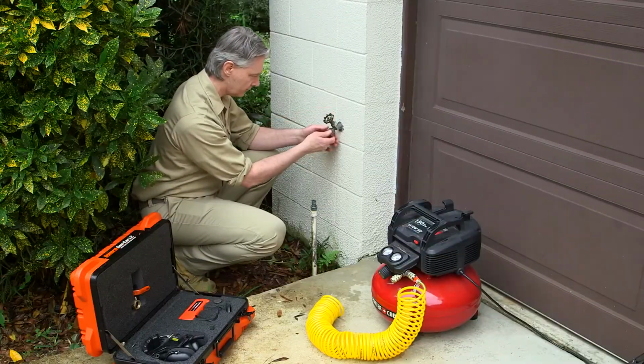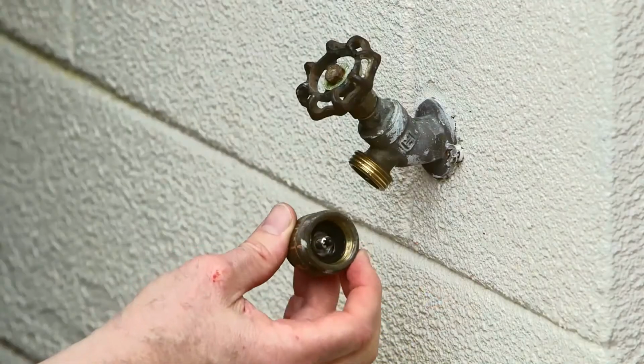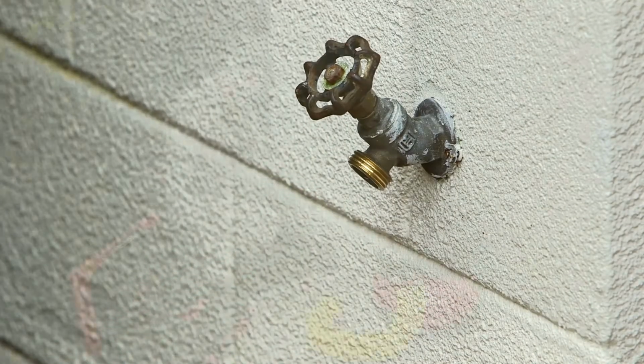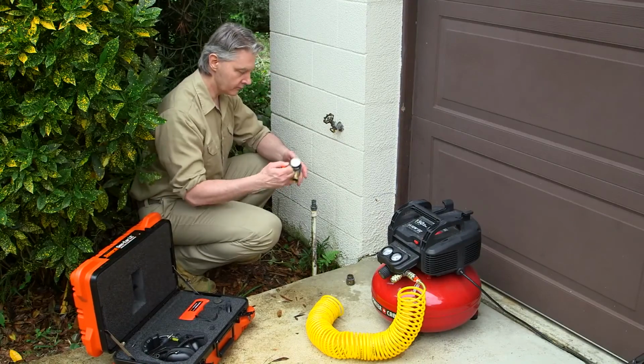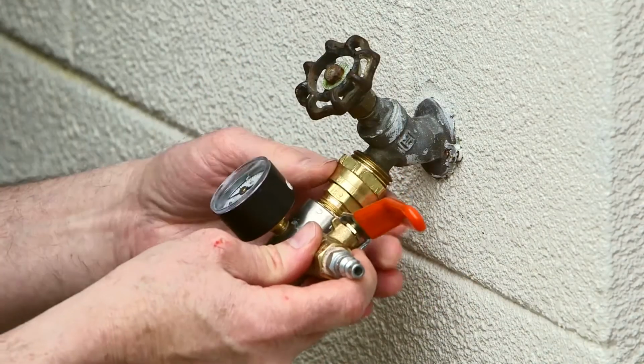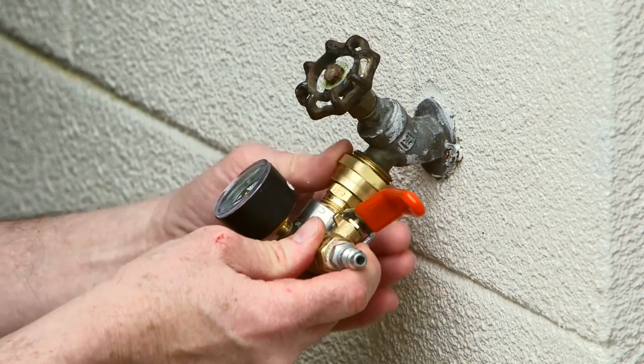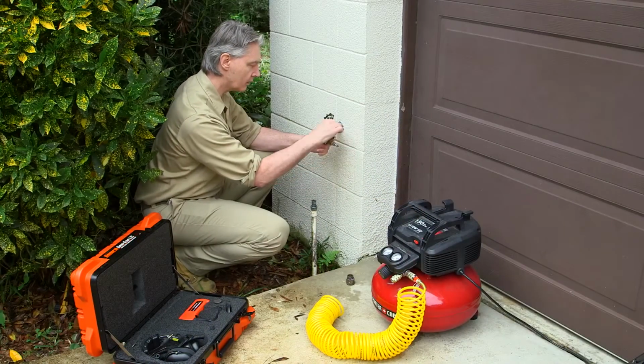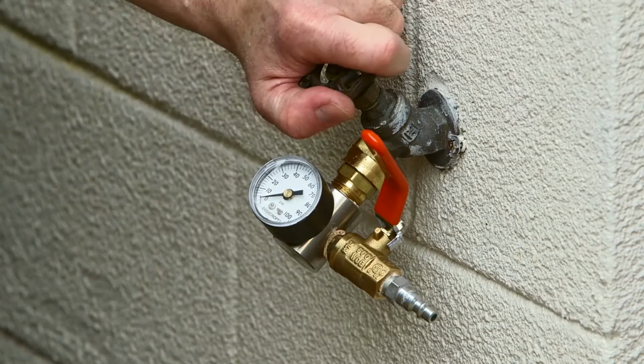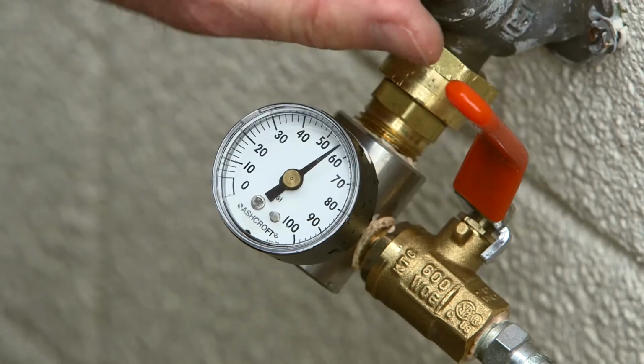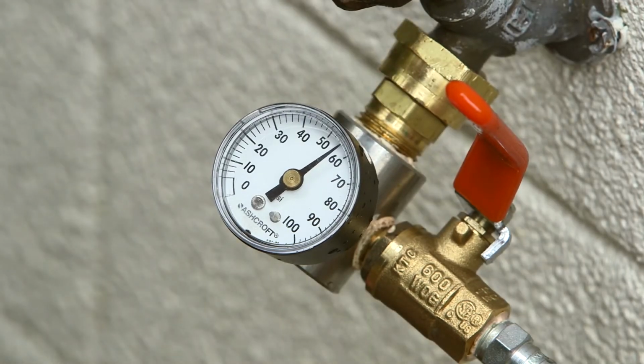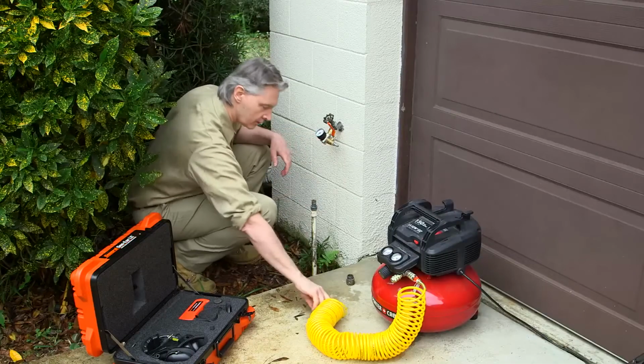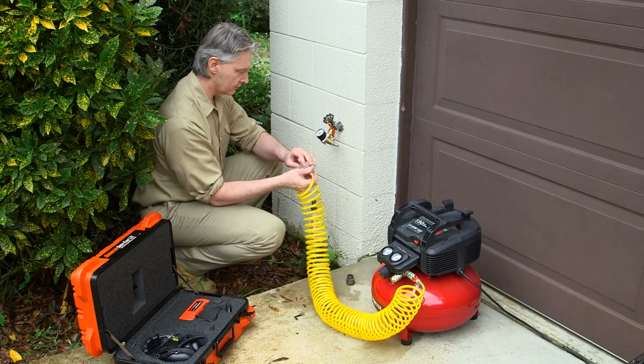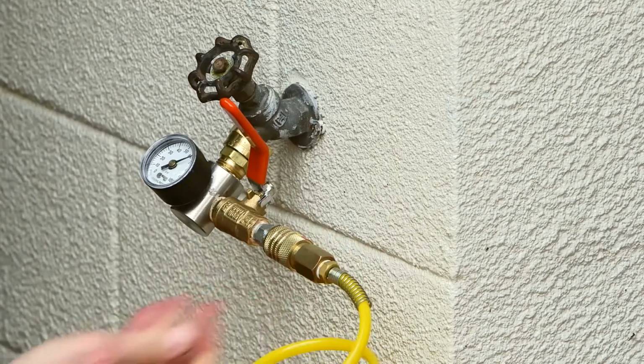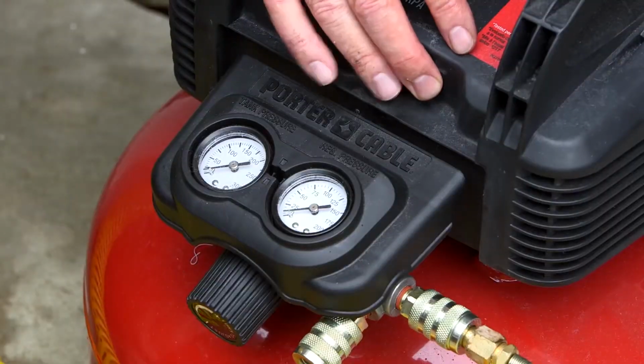Go to a nearby hose bib. If there is a backflow check valve, remove it. Thread the SAM onto the hose bib. Make sure the SAM air valve is closed. Then open the hose bib valve. The gauge will indicate the building's water pressure. Attach an air compressor to the inlet of the SAM. Turn on the air compressor.